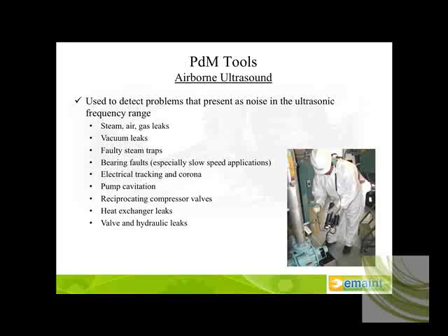Electrical tracking and corona can be heard with ultrasound, as well as pump cavitation, heat exchanger leaks, valves, and hydraulic leaks. The picture you're looking at here in the lower right-hand corner is a pretty good example of the use of contact ultrasound in a lubrication program on a slow-speed rotating piece of equipment. The gentleman actually has two capabilities here. He is listening to the grease being inserted into the outboard bearing of this pump so that he can hear the audible tone as the grease is being injected through the Zerk fitting. A real good application of the contact ultrasound.